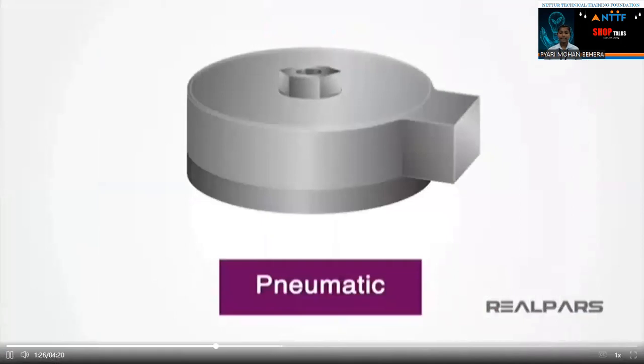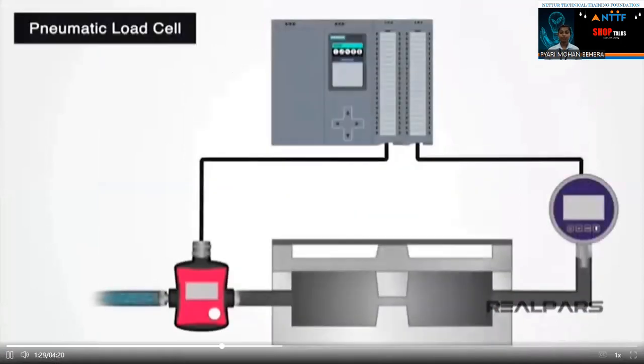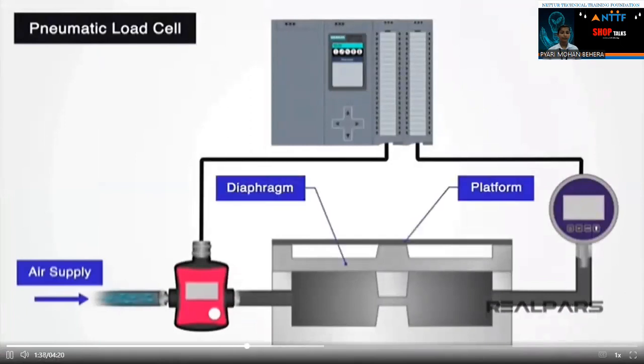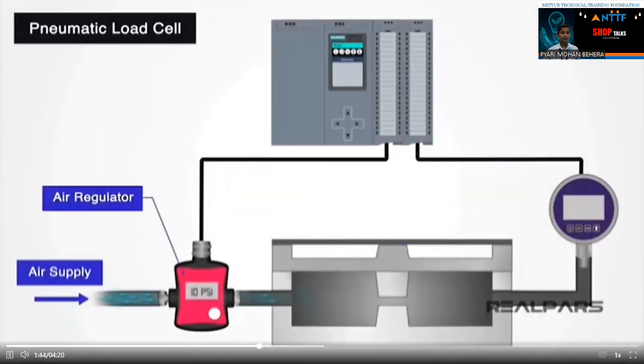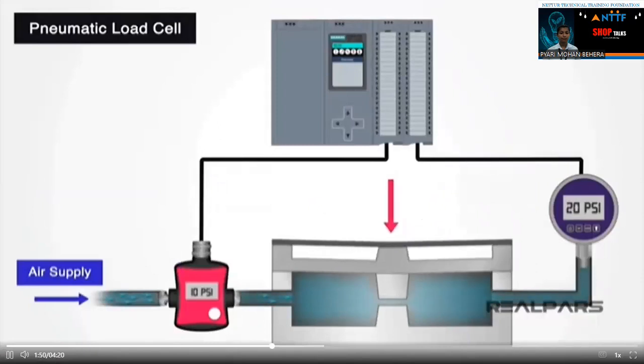Let's begin by looking at how a pneumatic load cell works. Since it is pneumatic, we know that it will deal with air pressure. A pneumatic load cell consists of an elastic diaphragm, which is attached to a platform surface where the weight will be measured. There will be an air regulator, which will limit the flow of air pressure to the system, and a pressure gauge. Thus, when an object is placed on a pneumatic load cell, it uses pressurized air or gas to balance out the weight of the object. The air required to balance out the weight will determine how heavy the object weighs. The pressure gauge can convert the air pressure reading into an electrical signal.